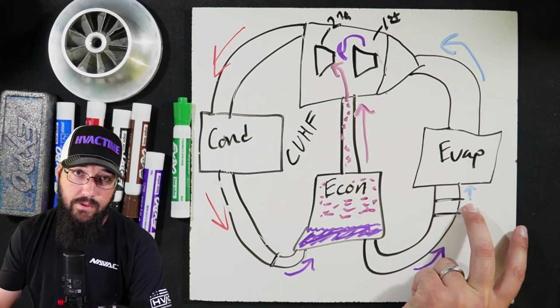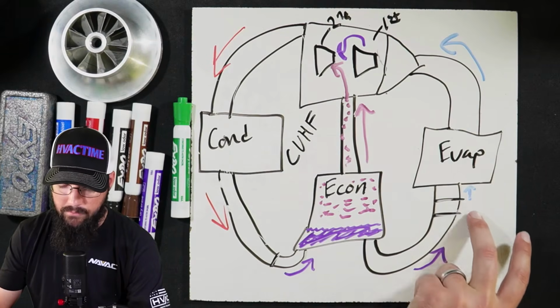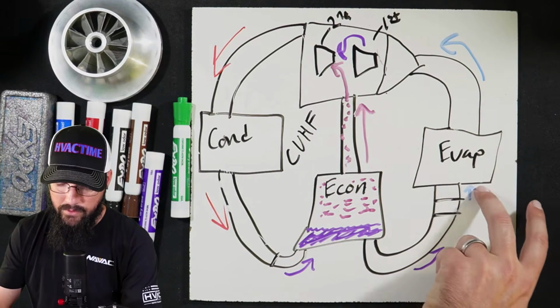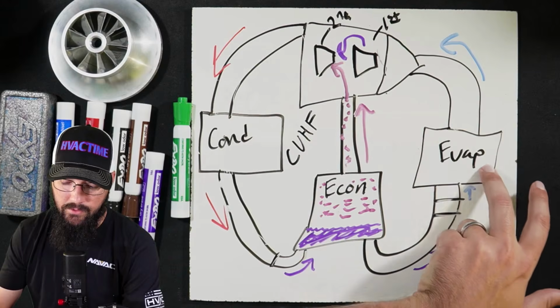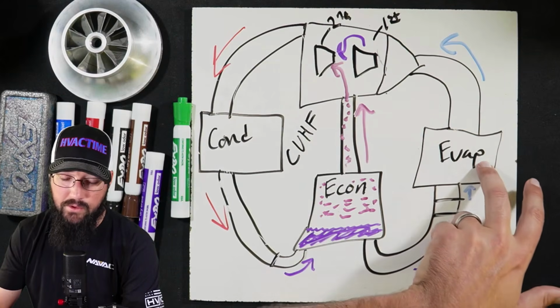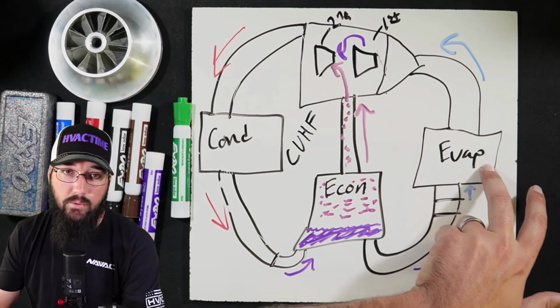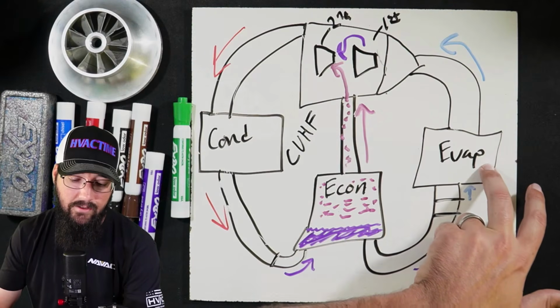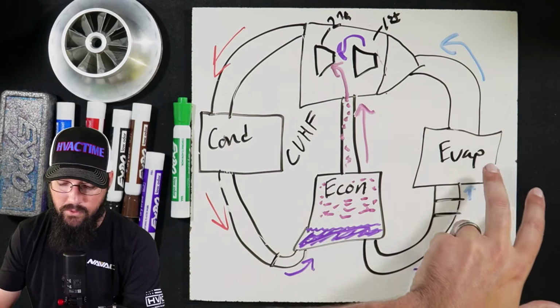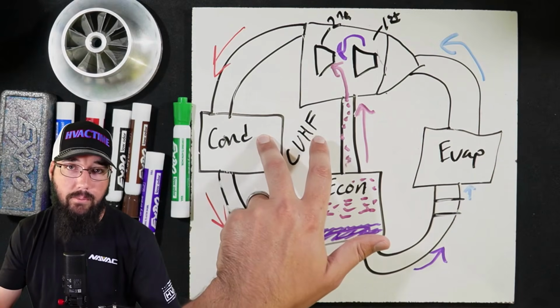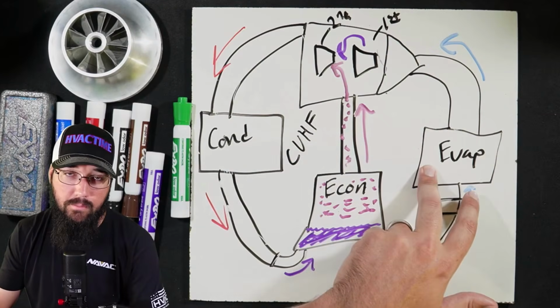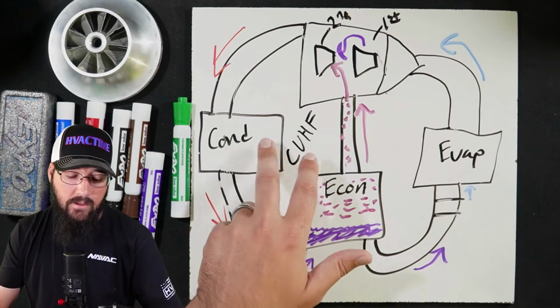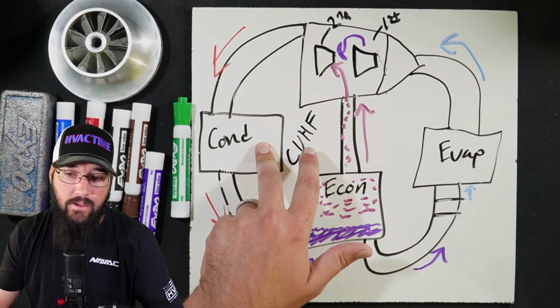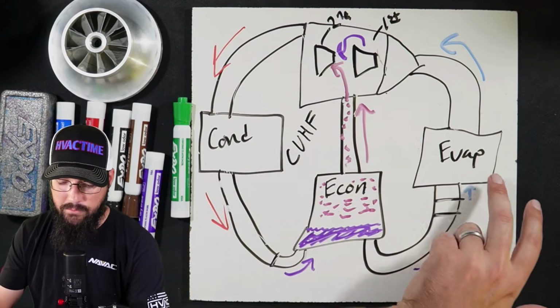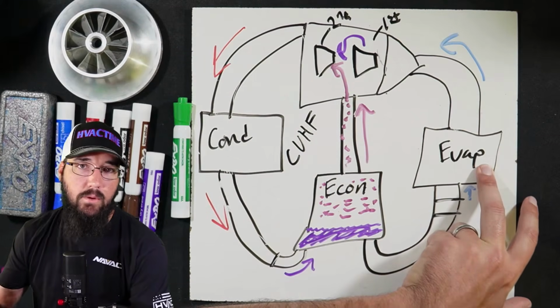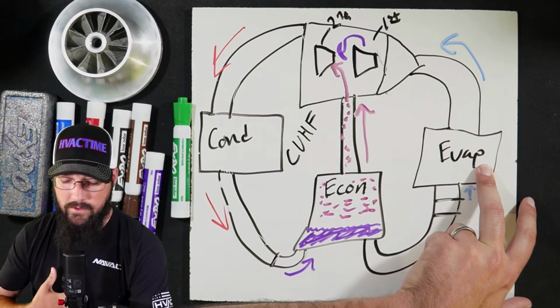So you'll go through both of these plates, and then we go from medium pressure liquid to a low pressure liquid on the other side of those plates. And these 2 plates finish that pressure reduction process to get us to a low pressure saturation so that we can take in heat. Because remember, our saturation is there just for taking in heat and rejecting heat. That's the whole point of why we have the saturation we do. We need it below our water temperature to take in heat. We need it higher than our water temperature to let go of the heat. That's our very fundamental refrigeration process. It's the same thing as what we'd have with air. We're just doing it with water in this case instead of air.